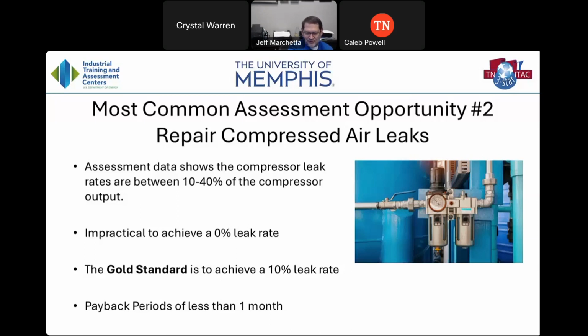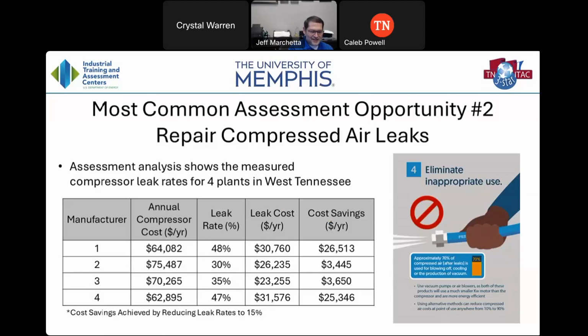Here you can see a picture of a regulator. Regulators are almost always a source of compressed air leaks, just because that's where a lot of fittings and connections are made in the compressed air line. So we see that a lot, and we get a lot of hits around those regulators. Next slide. So again, this shows you some of those costs. Column 1 there, again, these are directly from our assessment center here. We can see the annual compressor costs in that first column there, and some of the cost savings that we've identified in some of these facilities.